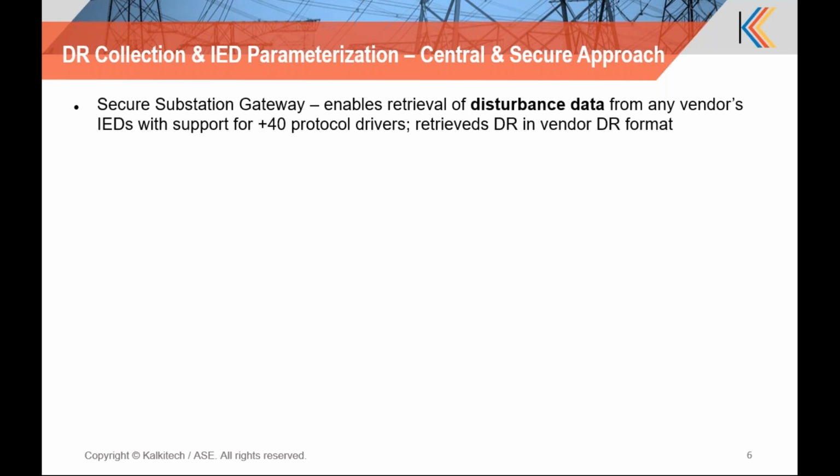It enables the disturbance collection in any of the vendor IEDs using the multiple protocol drivers available. We have around 40-plus protocol drivers dedicated to disturbance record collection, and it collects the disturbance record in the vendor format itself. The vendor format can be multiple.